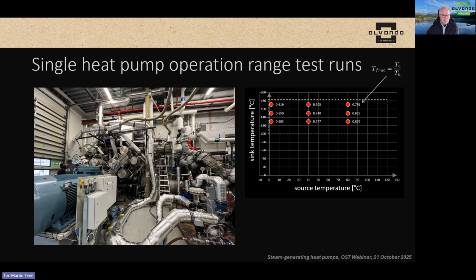So here I've drawn up the temperature range relevant for our heat pump. We managed to test different loads at these nine temperatures. This number here is the temperature fraction, the cold side divided by the hot side in Kelvin. I prefer to use the temperature fraction because it makes more sense thermodynamically than using the temperature difference.